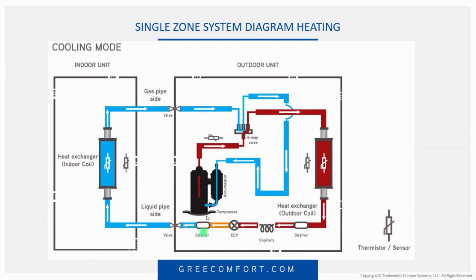Or if the line set's laying on the ground and you get it stuck in the mud and you get a little bit of dirt up in there, it don't take much and you're going to end up with plugged up strainers. So just take a little time to be careful with what we're doing, and make sure you're covering the pipes up when you're installing them.